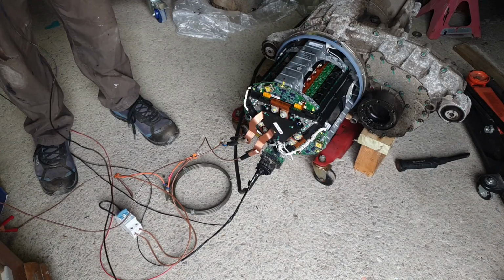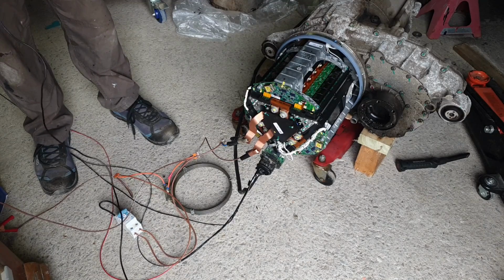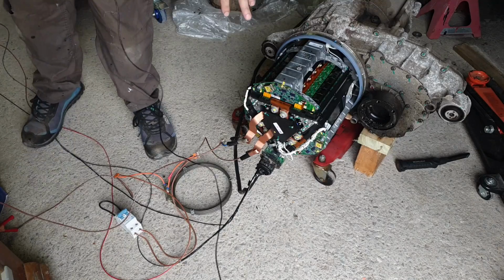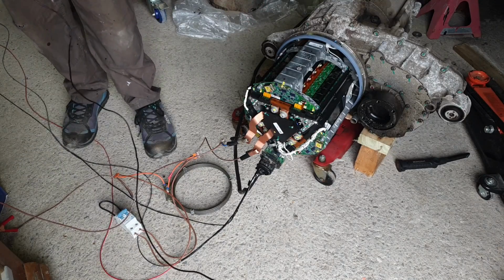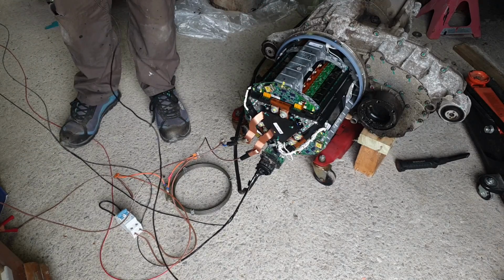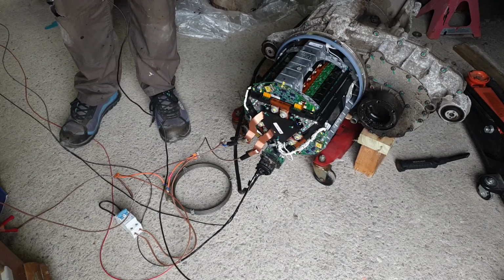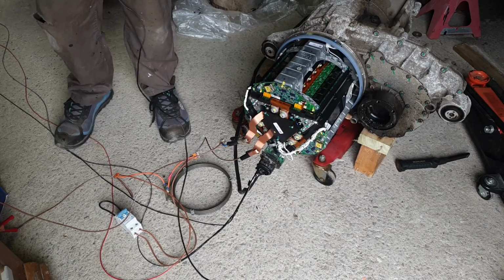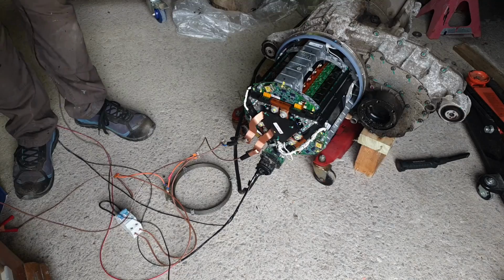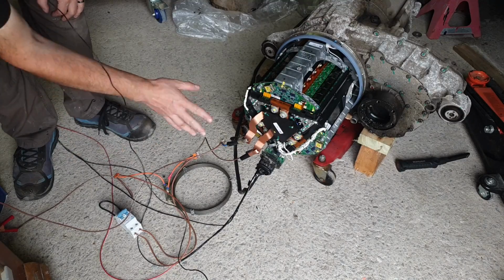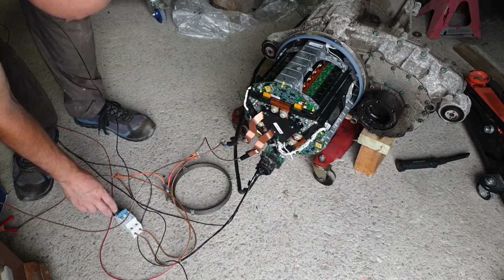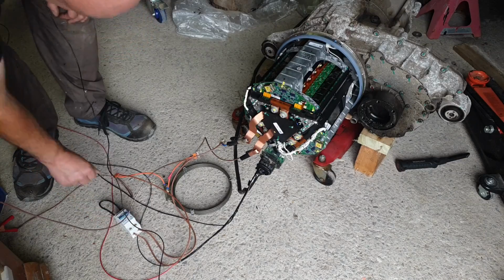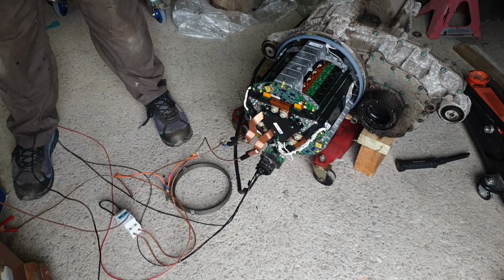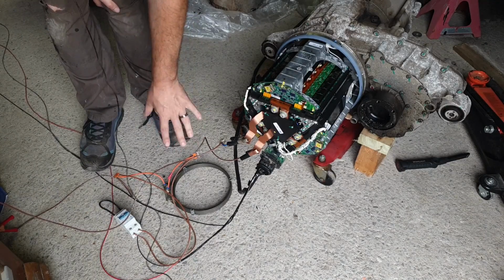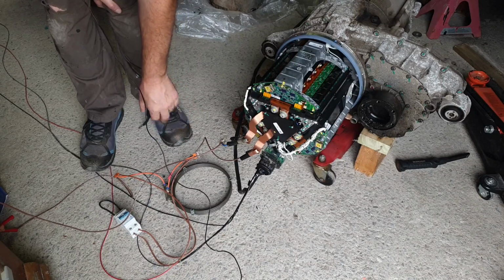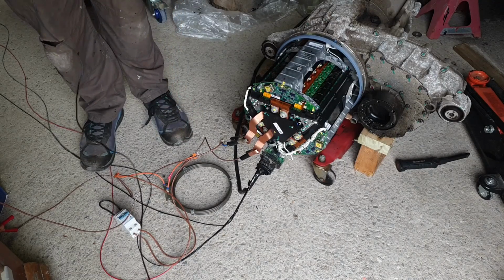And indeed, I am now showing just over 42 volts on my DC bus. So there was a very valuable reason that you may want to do that. So, last part of the puzzle now that we have everything confirmed, the reading voltage, I'm going to close my circuit breaker. I have now bypassed the heating element, but it is still there in the event of an emergency.